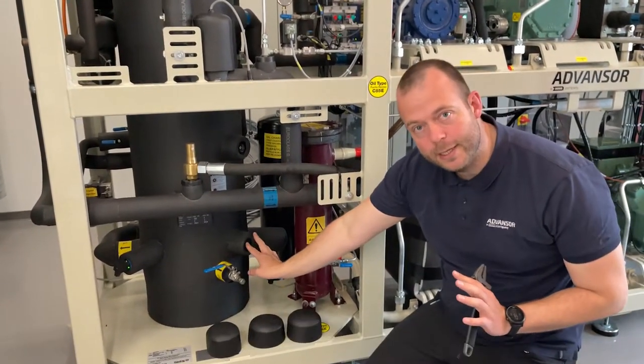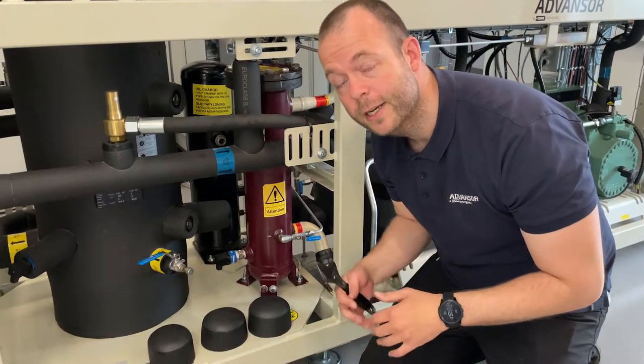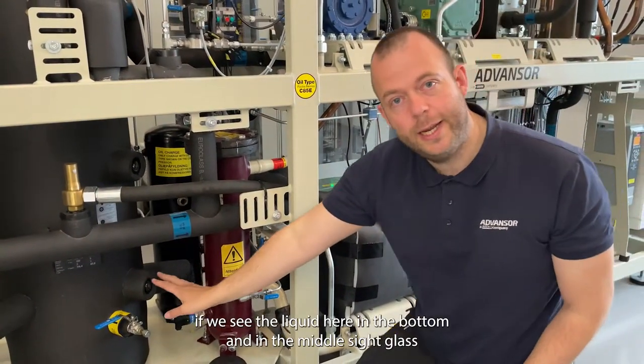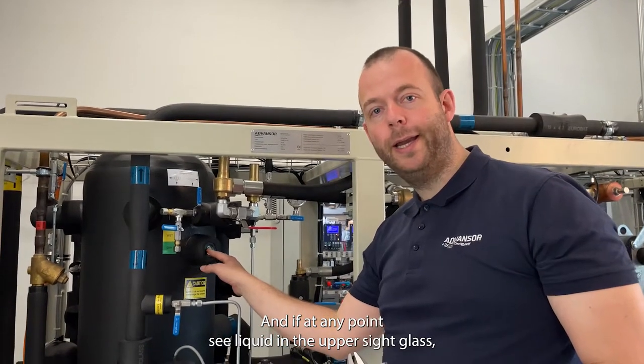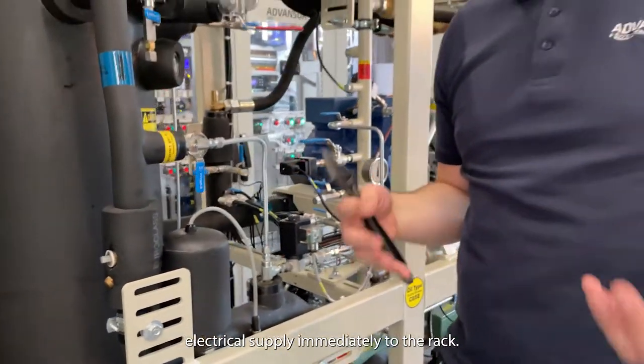Then we need to watch the receiver — we need to watch the sight glasses to see where the liquid level is. When you are looking into the sight glasses, it is important to look straight into them. As we can see now, there is no liquid yet in the bottom sight glass. We need to wait and see. If we see liquid in the bottom and in the middle sight glass, then we need to watch the upper sight glass. If at any point we see liquid in the upper sight glass, we need to close the valve in front of the gas bypass valve and then immediately shut off the electrical supply to the rack.